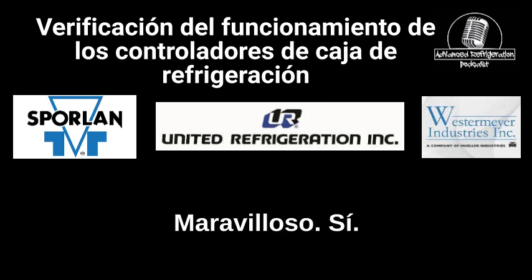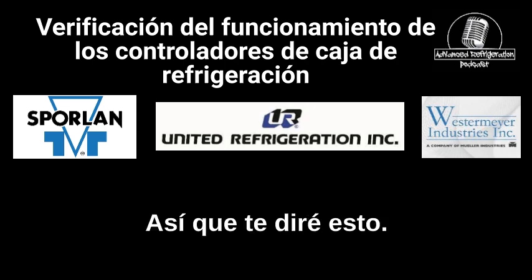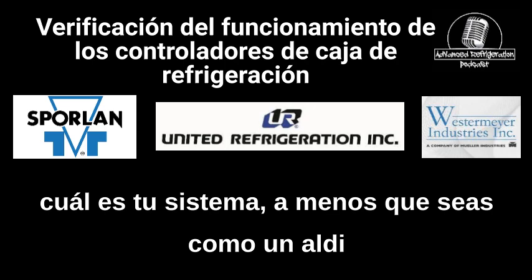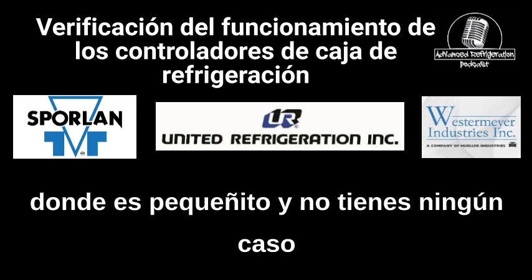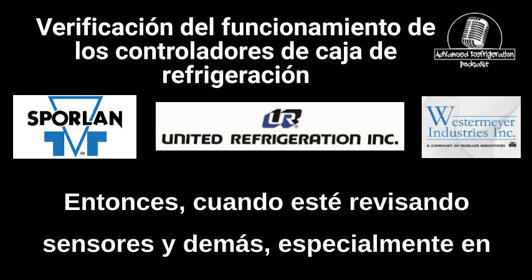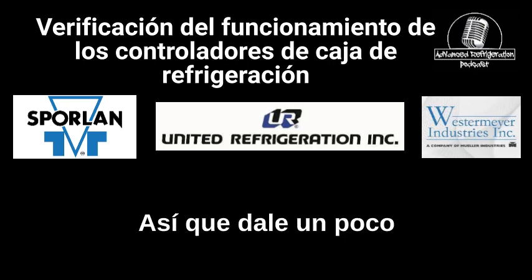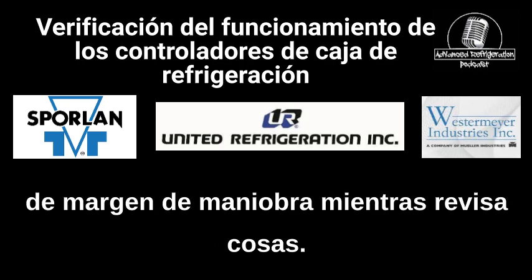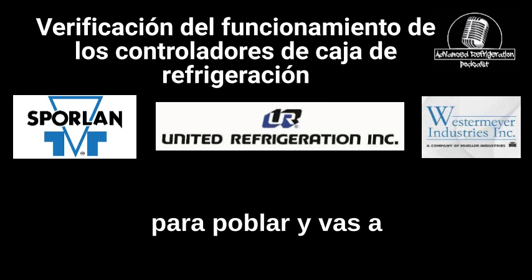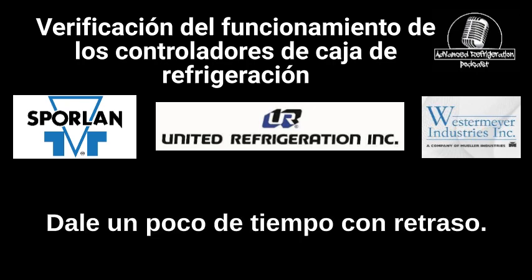Oh, wonderful. Yeah, but let's go over how to verify this stuff, guys. So, I will tell you this: case controllers, you're going to have lag. Depending on what your system is, unless you're like an Aldi, where it's tiny and you don't have that many case controllers, you're going to have lag. So when you're checking sensors on the E2 or other controllers, you're going to have a little bit of lag. Give it a little bit of leeway as you're checking stuff. Don't instantly think it's going to populate when you spray something with duster and it's instantly going to come down. Give it a little bit of time with lag.